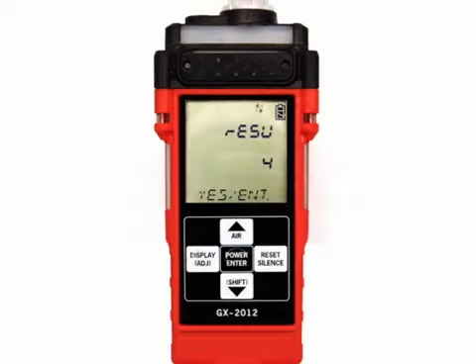the screen. If lunch break is turned on in maintenance mode, press and release the power enter button to continue accumulating time-weighted average TWA, peak readings, and time in operation from the last time the GX-2012 was used. The short-term exposure limit STEL reading is reset each time the GX-2012 is turned on. Press and release the display adjust button to reset the accumulation of these measurements. If you do not press the power enter or display adjust button within 5 seconds, the GX-2012 automatically resumes accumulating the TWA peak readings and time in operation.